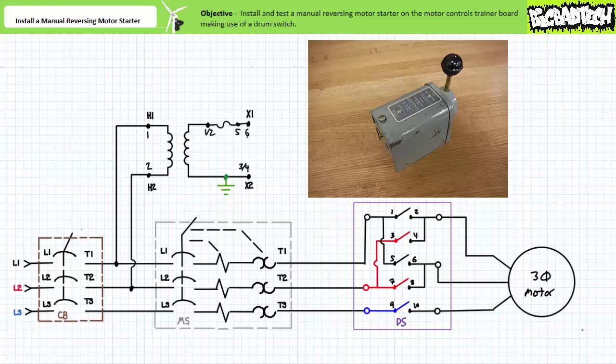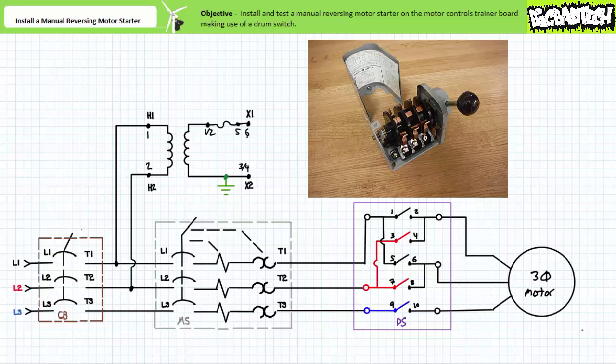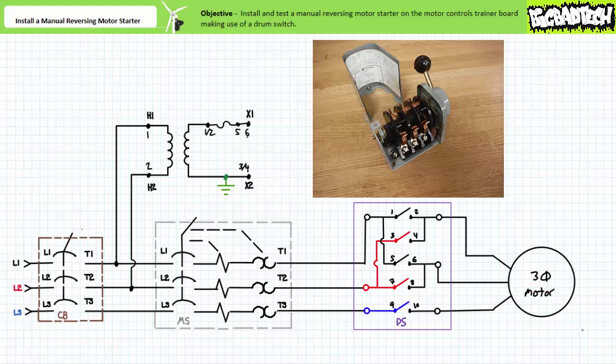This particular drum switch is something I scavenged. The wiring diagram shows no connection is made in the center off position. In the forward position, applied phase sequence as seen by the motor is such that it rotates in one direction. In the reverse position, applied phase sequence as seen by the motor is such that it rotates in the opposite direction.